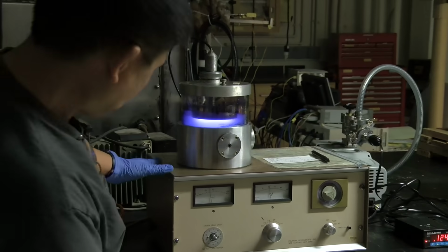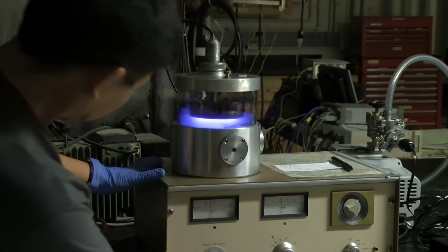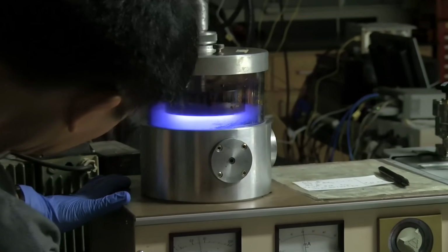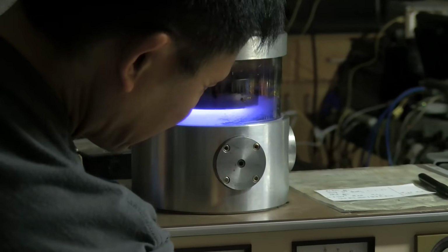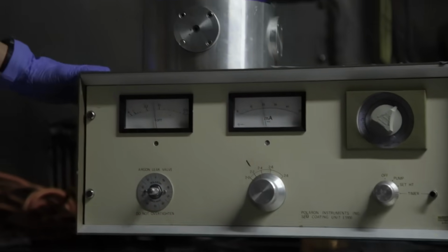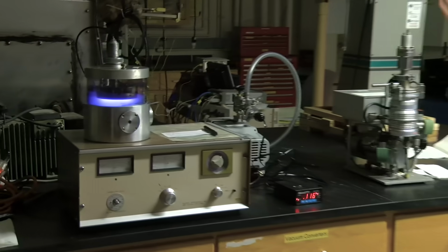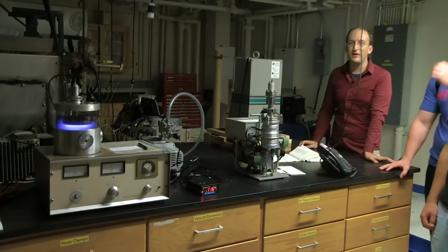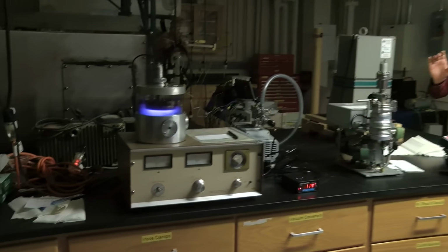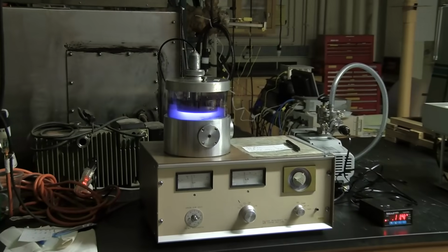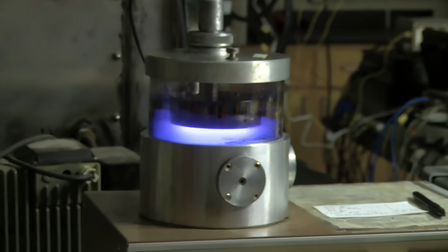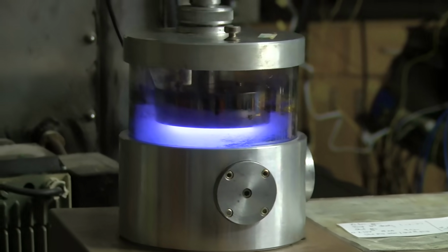There are a few other things to note. Remember how we talked about charged particles having a certain range in matter? Well, low energy particles in the keV range do not have a very high range even in gases, which is why Reed has this vacuum pump connected. Otherwise, the argon wouldn't make it to where it has to do the damage. When there's too much gas in there, it shuts off. When there's not enough argon in there, there's no argon to do the damage. So we're accelerating about 2 keV ions, and their range is higher than the distance they have to travel, so they make it where they're supposed to go. This is a direct application of NSE, along with a fair bit of high voltage electronics. And that's pretty much all there is to it.